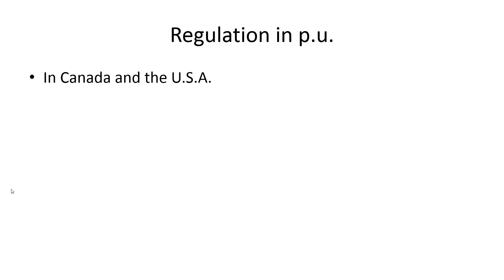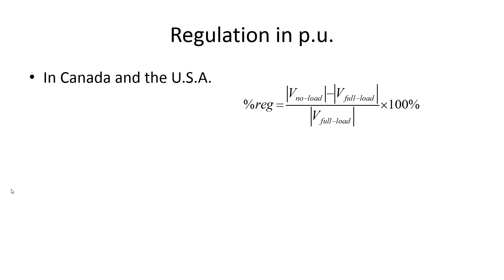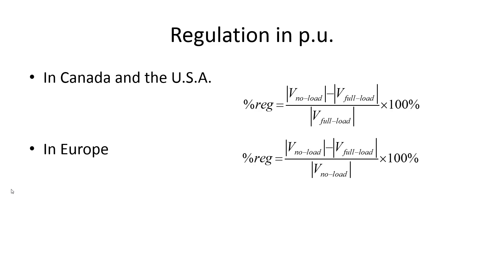Voltage regulation. We compute the regulation of a transformer by measuring the voltage at the terminals when fully loaded, then disconnecting the load and measuring the no-load voltage. In Canada and the US, the regulation is the difference divided by the full load voltage. In Europe, the same difference is compared to the no-load voltage. That's why the same transformer has different regulation values across the Atlantic.